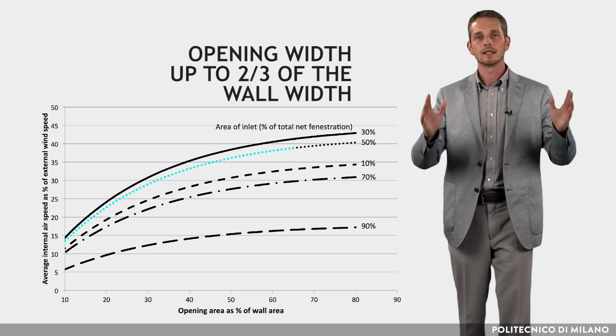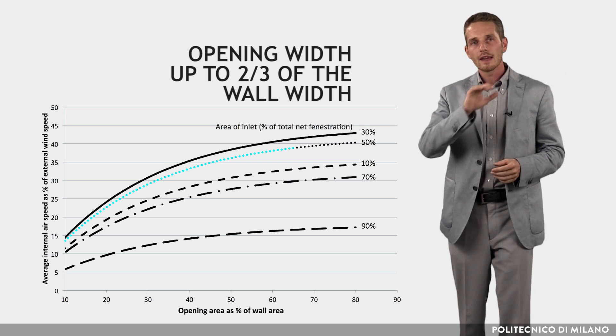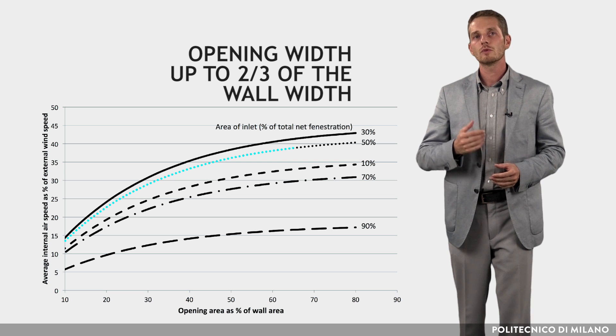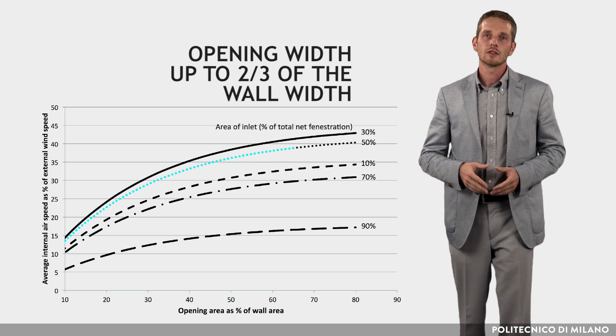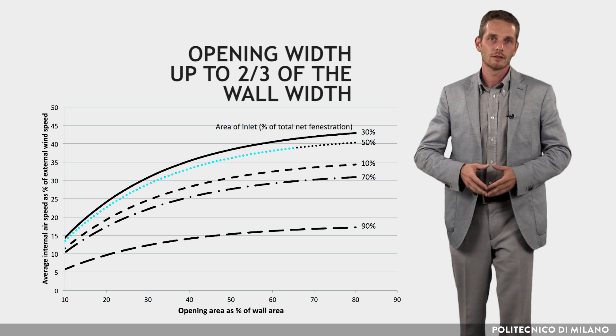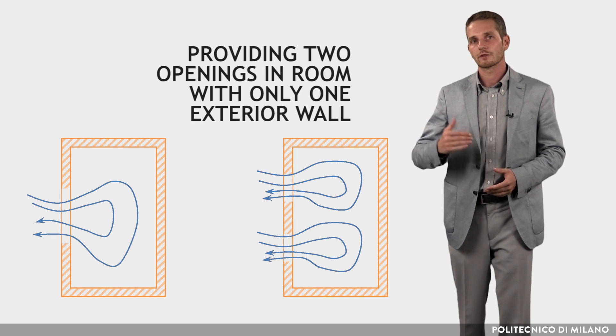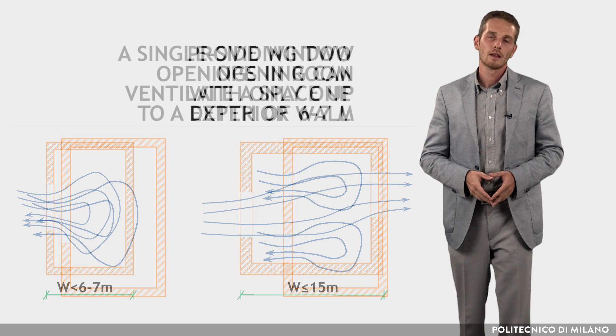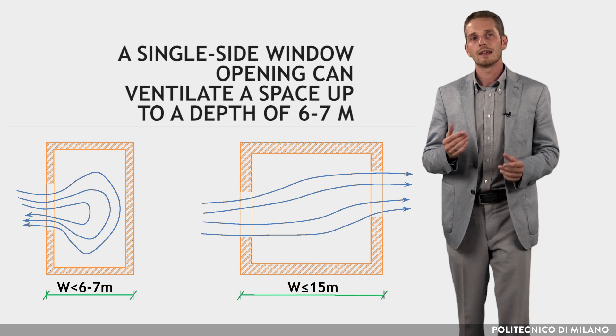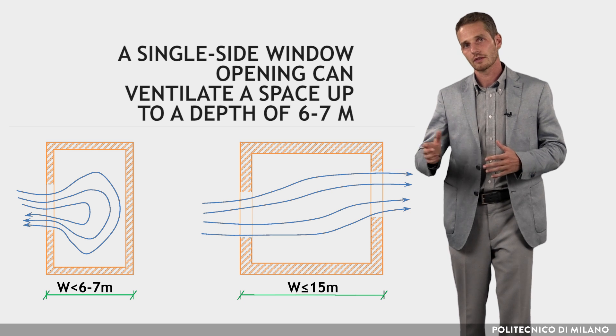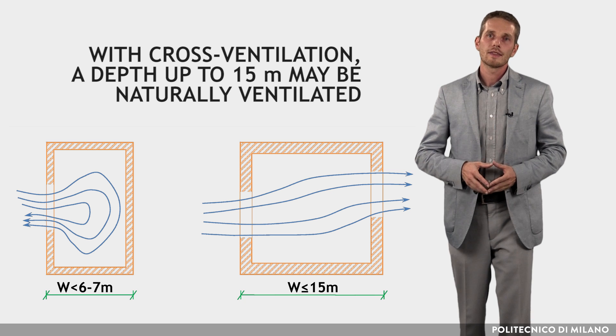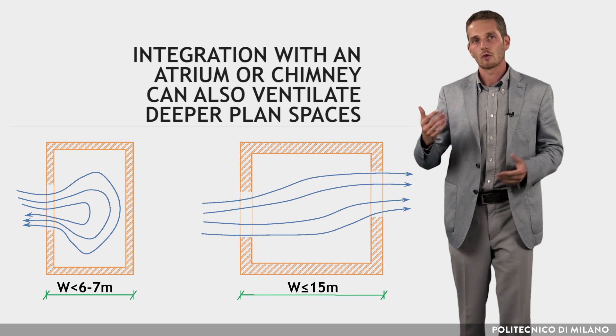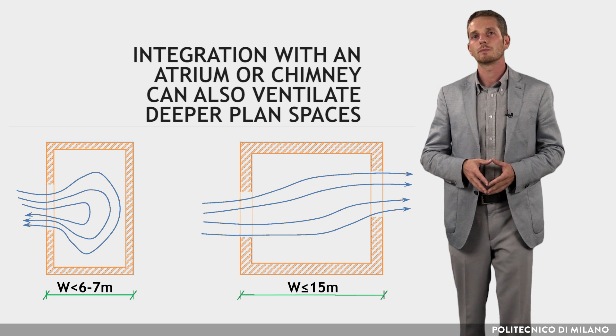In rooms of normal size which have identical windows on opposite walls, the average indoor airspeed rises rapidly by increasing the width of the window up to two thirds of the wall width. Beyond that, the increase in indoor airspeed is less effective. In the case of rooms with only one wall exposed to outside, provision of two windows on that wall is preferred to a single window. A single side window opening can ventilate a space up to a depth of 6-7 meters, while with cross ventilation, a depth up to 15 meters may be naturally ventilated. Integration with an atrium or chimney to increase the stack effect can also ventilate deeper plan spaces.